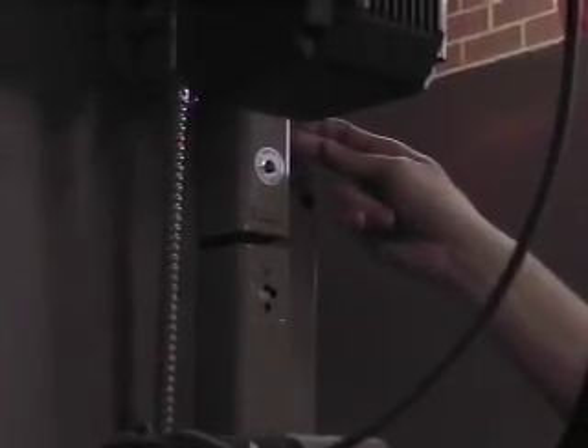The high limit controls, you've got two aquastats right here. This is going to be your first stage, and this will be your last stage. You guys know how these operate? You've got these on every boiler by code. Per code, you have to have 2 safeties. Technically, this controller acts as a safety. So technically, I wouldn't need both of these. You need one that's an automatic reset and then one that's a manual reset.